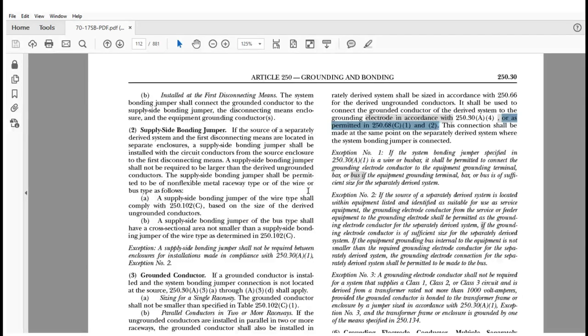Really, to me, it just allowed you to use the electrodes that are available. It doesn't create this issue with a separately derived system where you have to go to the water pipe or you have to go to the structural steel, and they have to be the nearest. The nearest part has been removed. So it really has no role, how far it is. Okay? So the nearest portion that was in that previous text has been removed.